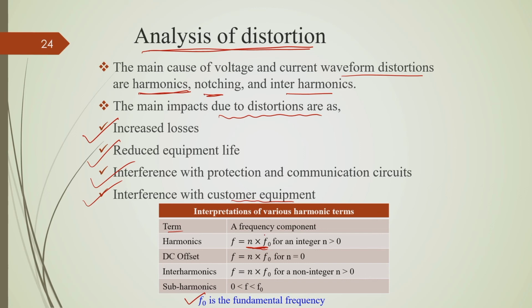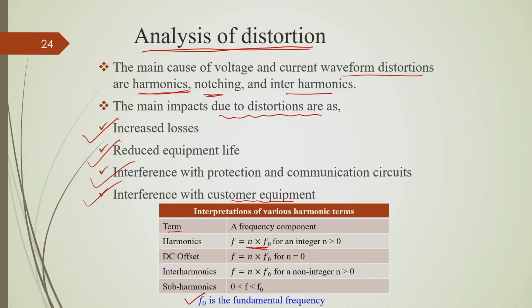And since we have an equal identical positive and negative half cycle, we do not have any even harmonics in power system, we mostly have odd harmonics. So, n is of odd number. So, we are concerned of some higher order odd harmonics like third harmonics, fifth harmonics, seventh harmonics, 11th harmonics and up to that. So, those harmonics we need to study, and we need to have some mitigation approach for those harmonics. So that the total harmonic contents will be lower, and we will get supply voltage as sinusoidal as possible.